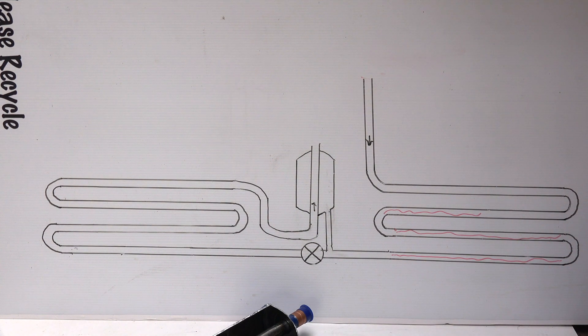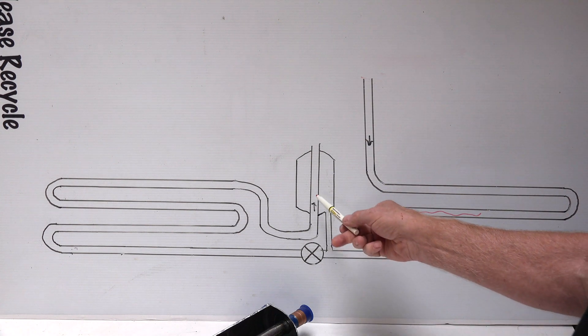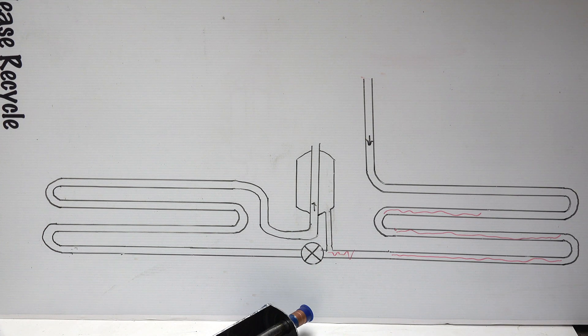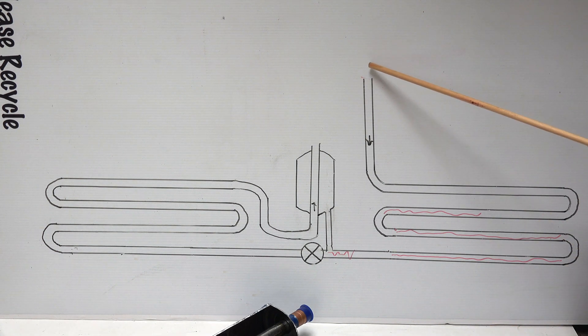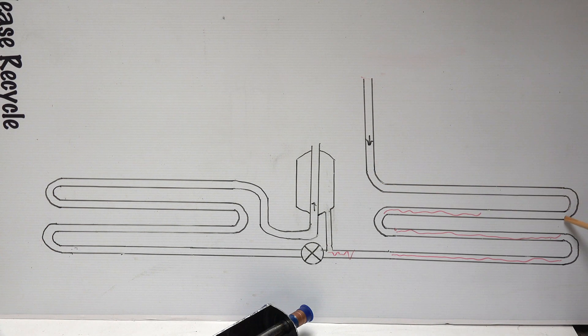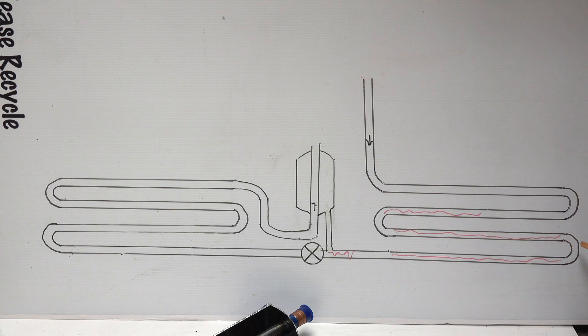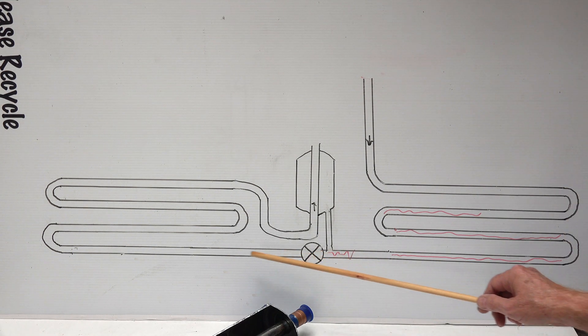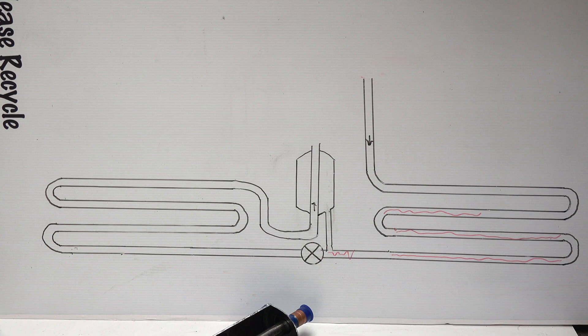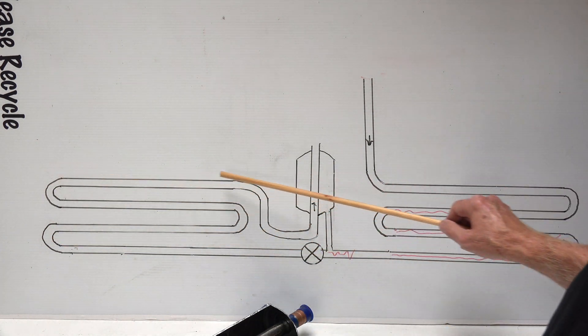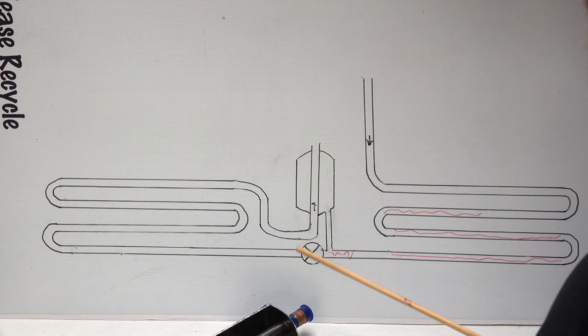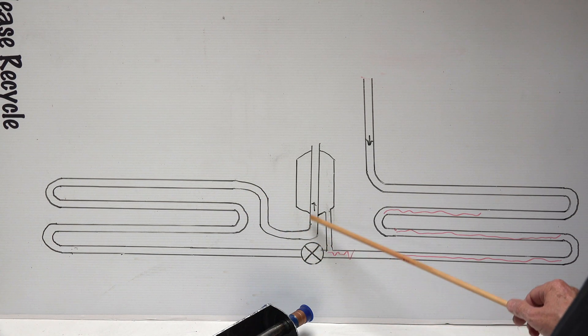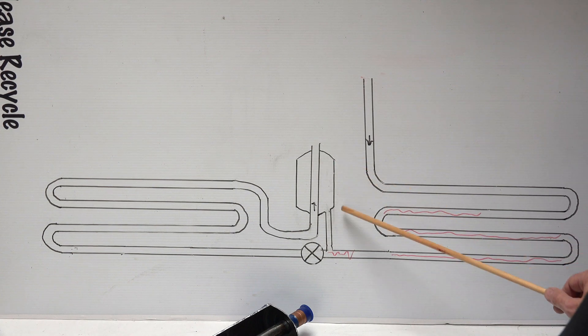So what do we do? In comes the charge compensator. So let's look with what happens in heat mode. The hot gas is coming in here to the condenser that's inside the house. It goes through and it's being fed through the TXV to the evaporator, which is the outdoor coil. Goes through the coils of the evaporator, and because the TXV works on superheat, it will have a certain amount of superheat, but it will be cold, much colder than the liquid line.